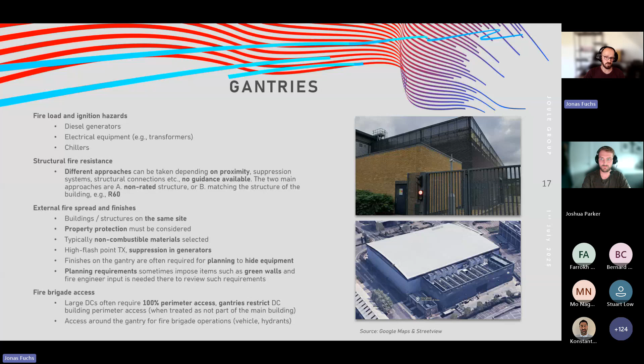The materials on site, the hazards that are present, are diesel. There's also a lot of refrigerants and coolants involved in the mechanical cooling equipment. There are also battery rooms. The two prevailing technologies used are valve-regulated lead acid (VRLA) or lithium ion. Lithium ion seems to be on the rise, but we still see both technologies almost equally used. There's also an involvement of firefighter water runoff, which needs to be considered specifically for lithium ion, as well as any potential diesel contamination. Then there are transformers and HV equipment and loading bays.